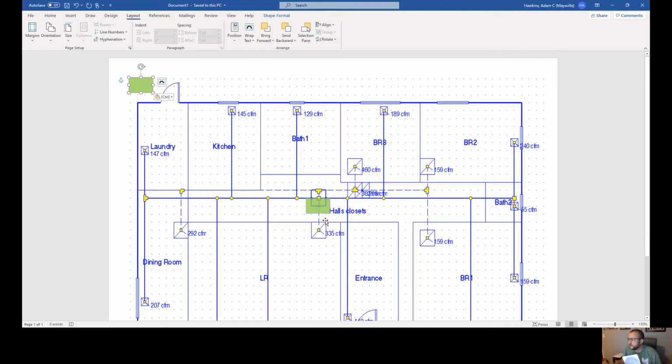All right, so I'm going to go to my ductulator. I'm going to stay at 0.1, and I'm going to say the first piece of duct needs to be what size? Well, we already sized that. So the first piece of duct has to go in the middle of the air handler. So this is your first piece. And that piece of duct has to handle everything the air handler blows, which is 800 cubic feet per minute in this case.